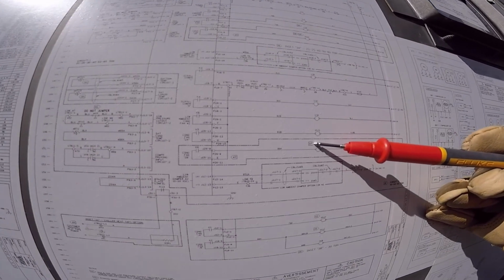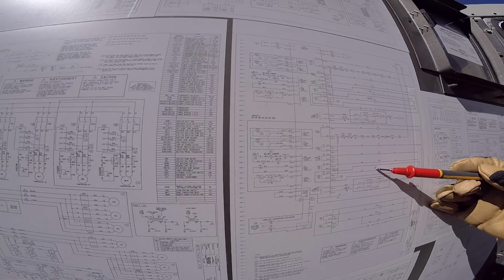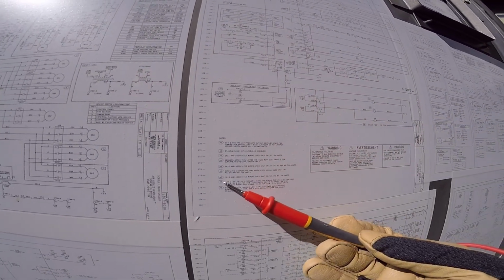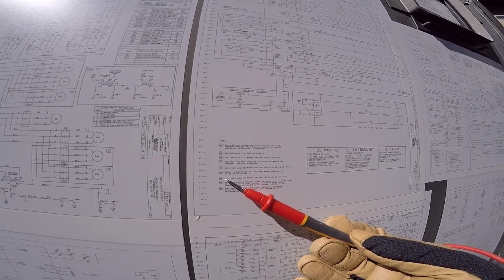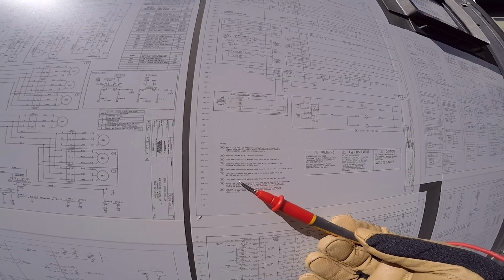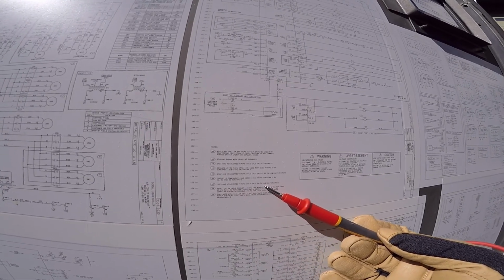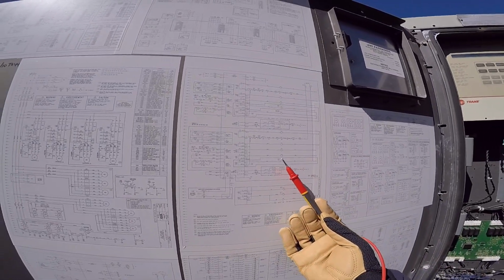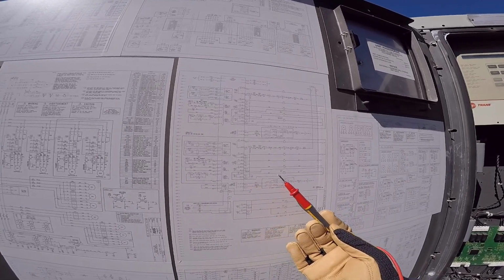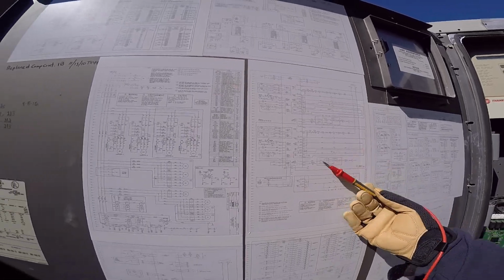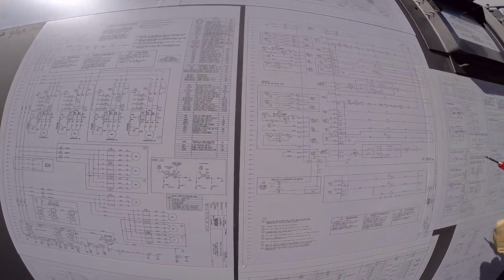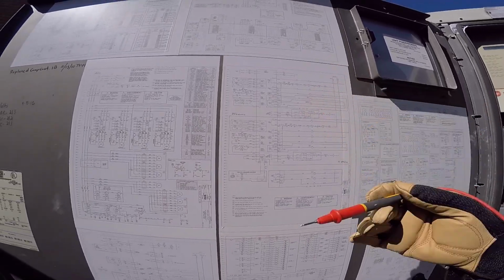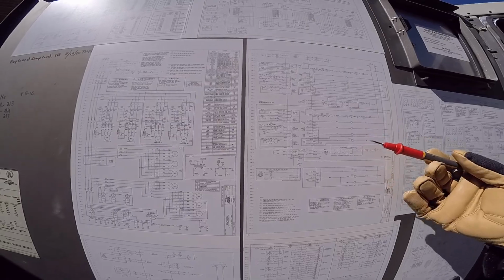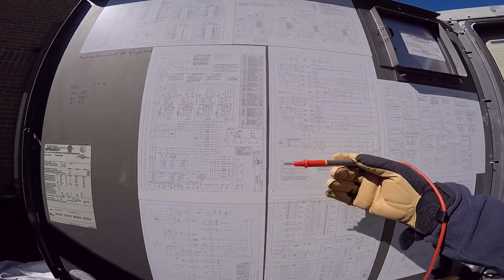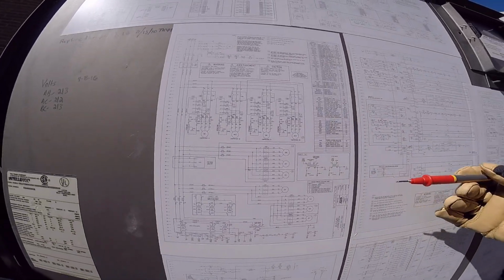Looking closely, you'll see there's a little tab here that says 47. You can come down to where you find the 47 in the notes and read, and it says this 1K13 and associated wiring is used only on 50 and 60 ton units. So if you don't have a 50 or 60 ton unit, this section of the ladder, this boxed out part right here, doesn't apply to you. You need to know what you're working on. You need to keep in mind when you're reading your schematic, even if you land on the chiller you're supposed to be on and you see that note, you'd better check the notes and make sure that it applies to you. So you need to keep all that in mind.